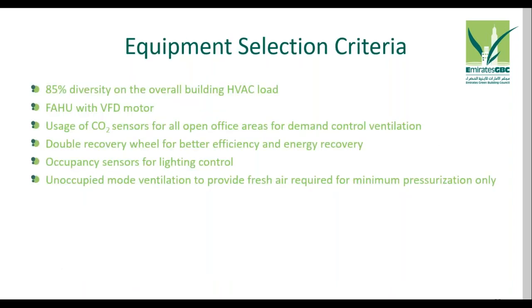We are talking about fresh air, which has to do with VFD motors, because for diversified occupancies we go with demand control ventilation. For demand control ventilation, we need to have varying speed or varying quantity of the fresh air. When we take these aspects, the starting current of the FAHU has to be improvised. The power consumption has to be brought under control. So FAHUs are with VFDs, which are recommended by ASHRAE 189.1.